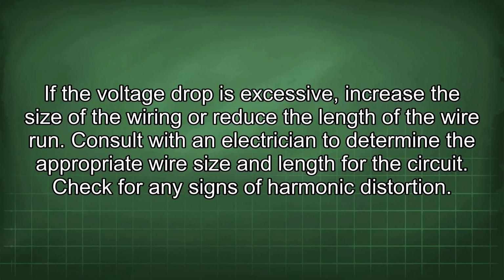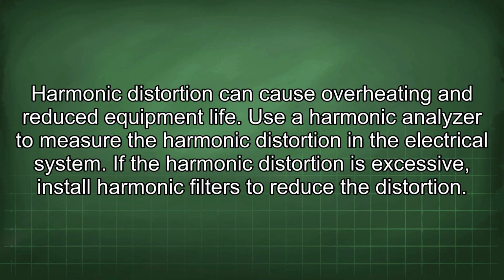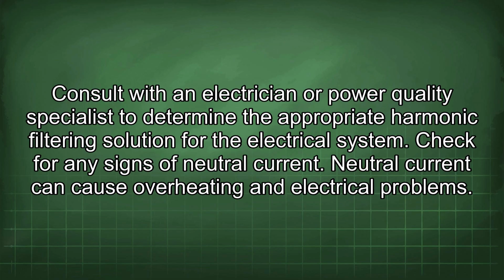Check for any signs of harmonic distortion. Harmonic distortion can cause overheating and reduced equipment life. Use a harmonic analyzer to measure the harmonic distortion in the electrical system. If the harmonic distortion is excessive, install harmonic filters to reduce the distortion. Consult with an electrician or power quality specialist to determine the appropriate harmonic filtering solution for the electrical system.